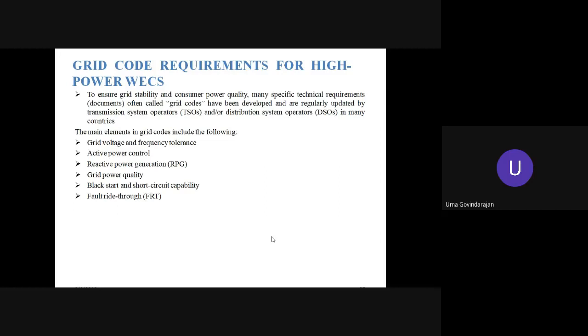Okay, to ensure grid stability and consumer power quality, many specific technical requirements, often called grid codes, have been developed and are regularly updated by the transmission system operators, TSOs, and the distribution system operators, DSOs. It depends at which point you are penetrating into the grid, whether in the transmission line or at the distribution end. Accordingly, we need to ensure grid stability and consumer power quality at the point of interface of the wind electric generator to the grid. If it is in the transmission line, it will be taken care of by the TSOs, and if it is on the distribution line, it is taken care of by the DSOs.